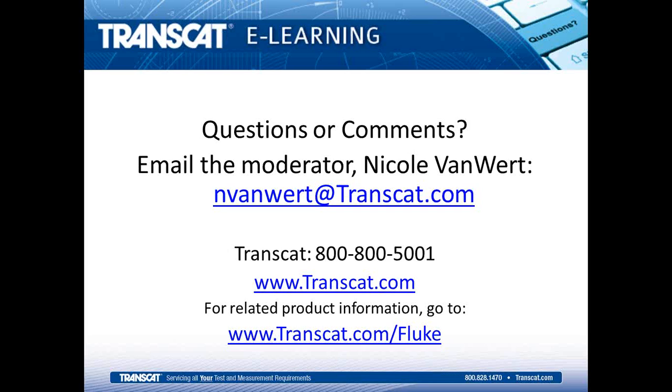Yeah, I think if I'm understanding the question right, it's the orientation of the dry block during that cal process is not critical. So if I needed to hold it horizontally or vertically or on an angle, that would certainly be okay. With that 9100, we see that used all over the place in factories and tight spaces, hard to reach spaces, and that's certainly okay to do.